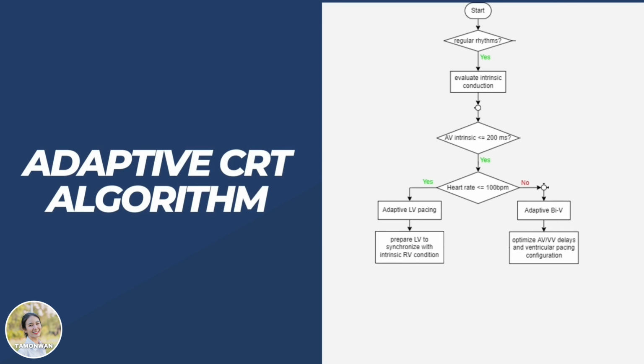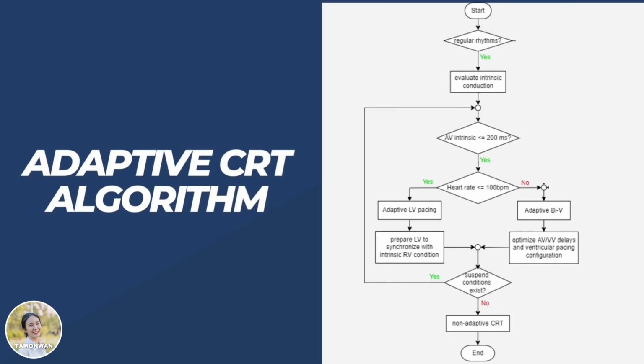For the adaptive LV pacing function, the left ventricle is the only chamber to be paced, at about 70% of the AV interval. And for the adaptive BIV function, the left and right ventricle are paced by optimizing the AV and VV delays. AV delay is adjusted to pace after 30 milliseconds of P wave, but at least 50 milliseconds before the QRS period. After that, check whether the suspend condition has existed in the last step or not. If yes, go back to check it again. If no, the non-adaptive function occurs.